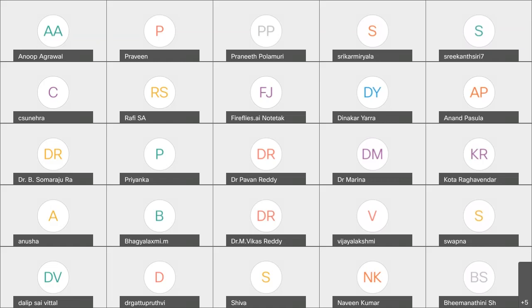If pressure is given as 5 only during expiration, and during the inspiratory cycle the machine senses a trigger, such as a flow or pressure drop when the patient initiates a breath, the pressure shoots up to give additional support. This is called IPAP during inspiration, with a different setting. So EPAP may be 5, IPAP may be 10 or 12. These are two different levels of PEEP that you are setting.